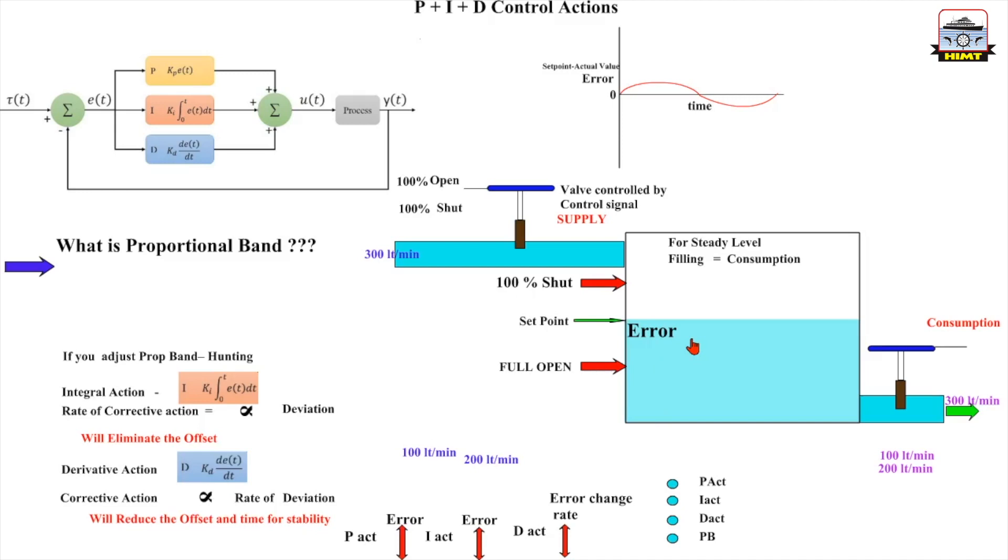On the basis of this prediction, this valve will continue to open more than what the P action would have done. It is anticipating a big drop in level. The outcome of this derivative action is that the stability point with or without offset is achieved quickly.